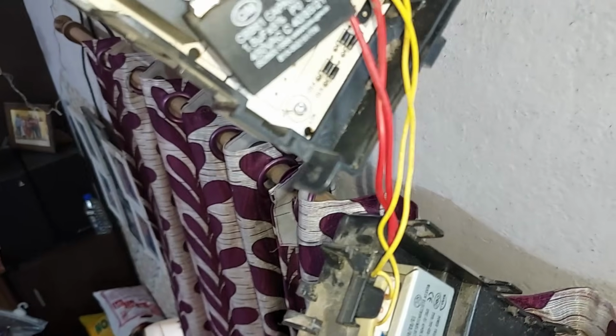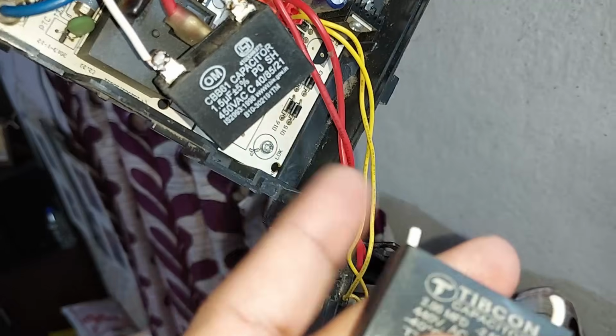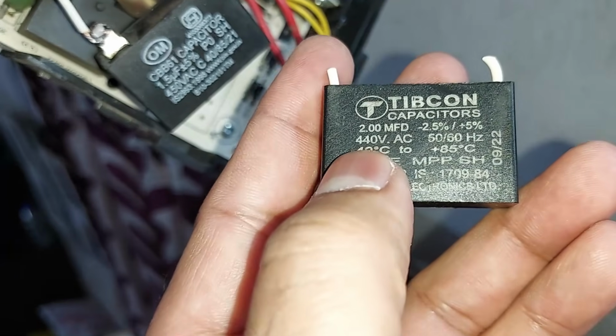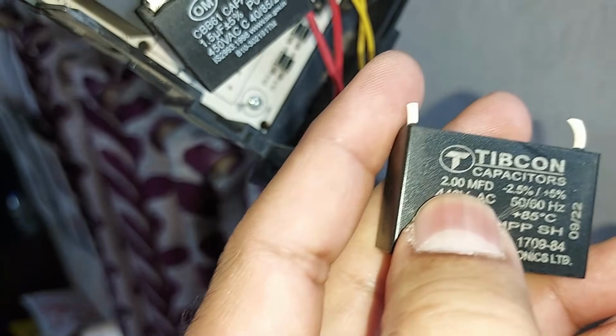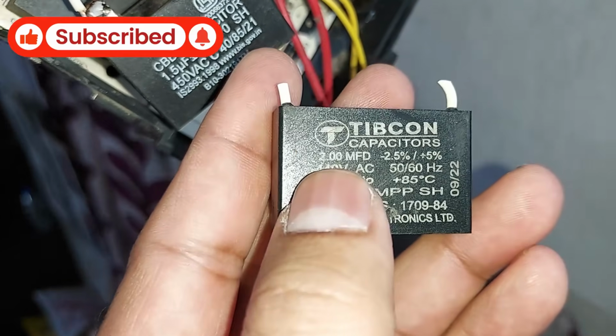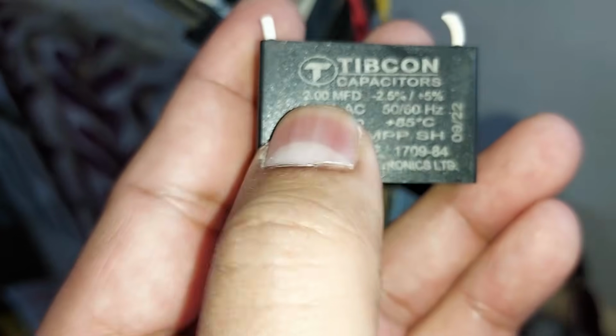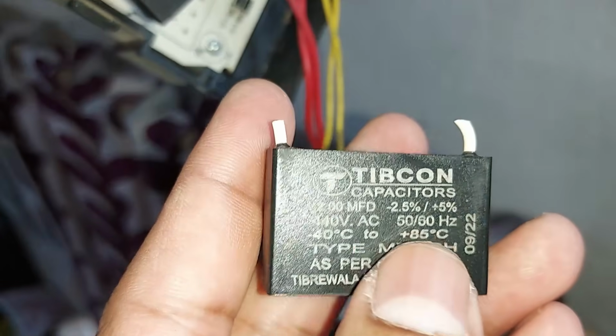We're going to turn this thing on and check it out. But let me tell you that when you're using capacitance, 0.5 doesn't matter that much. Instead of 1.5, you can use 2 MFD. That wouldn't do any harm to the motor or anything like that, because 0.5 doesn't matter much.